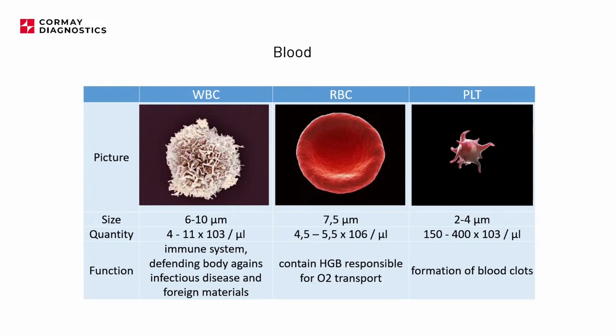So actually, when we want to make any measurements in the WBC channel, we need to destroy those red blood cells. And this is the action of the lyse reagent. Lyse reagent is dissolving basically the red blood cells. We don't want to see them in the WBC channel, because this will saturate the measurement, and the device will only see the red blood cells. It will not see any white blood cells because the number of those cells will be so big.